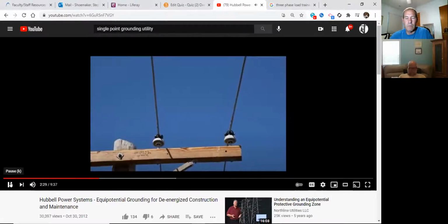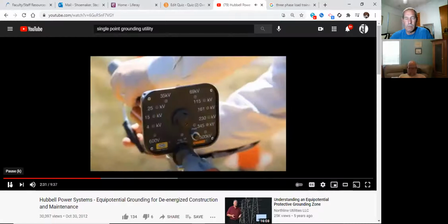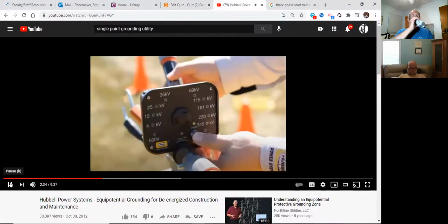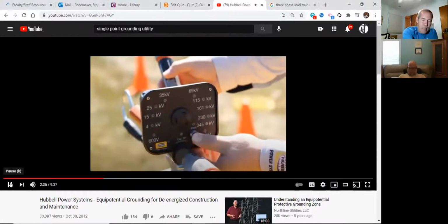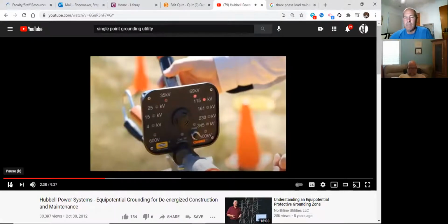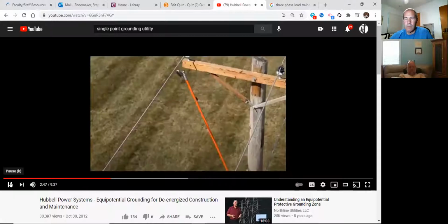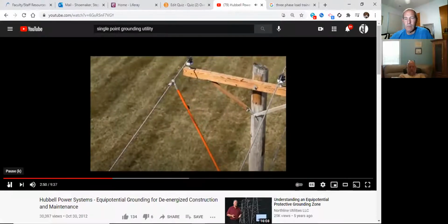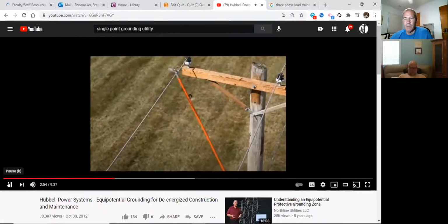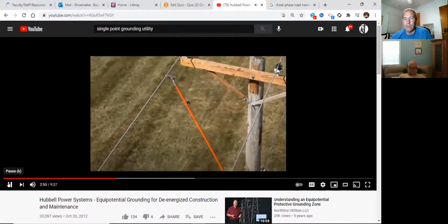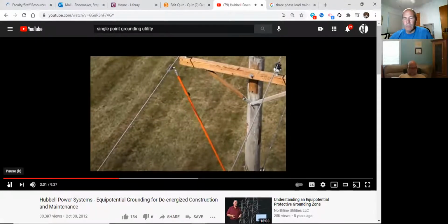Sent back down to the groundman, the auto-ranging voltage indicator is rechecked to confirm that it was operating properly. He again uses a separate tester to activate the auto-ranging voltage indicator. Notice how it sequences through a series of all display ranges, verifying its full functionality. Next, a tubular wire brush mounted on a universal stick thoroughly cleans all conductors at the places grounding clamps will go later. This is absolutely essential. It removes oxides and contaminants so the grounding clamps can make good connections.